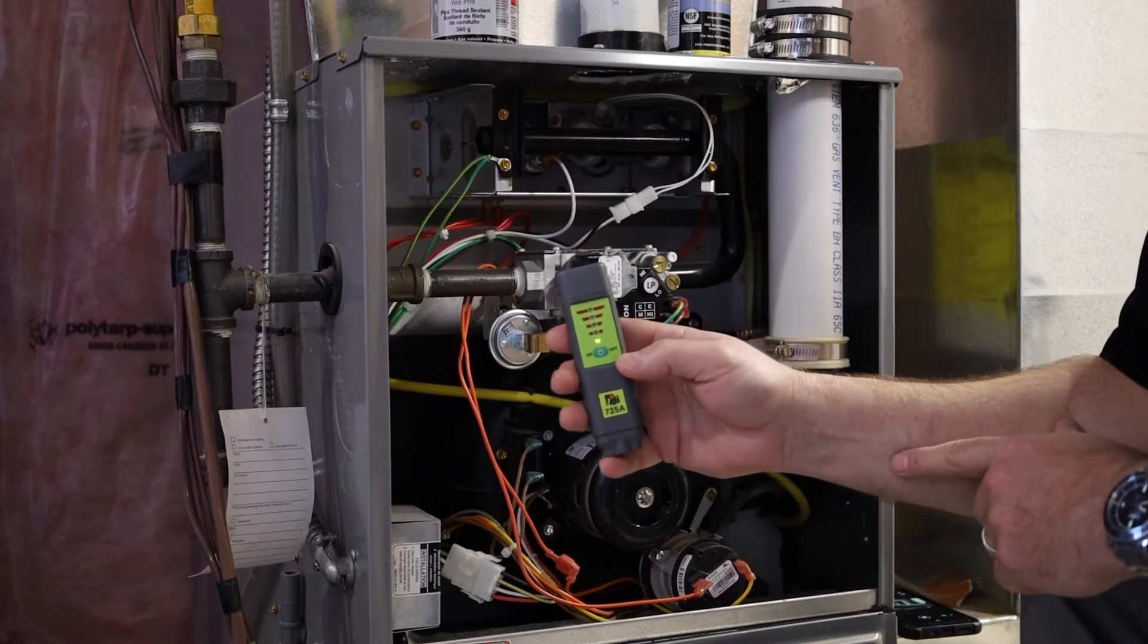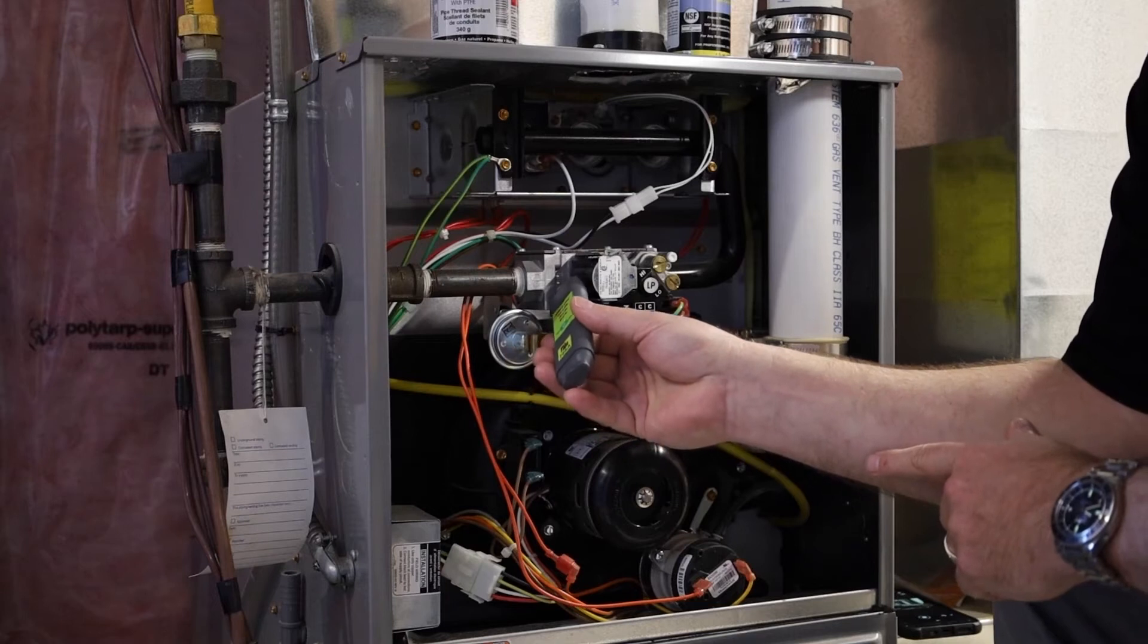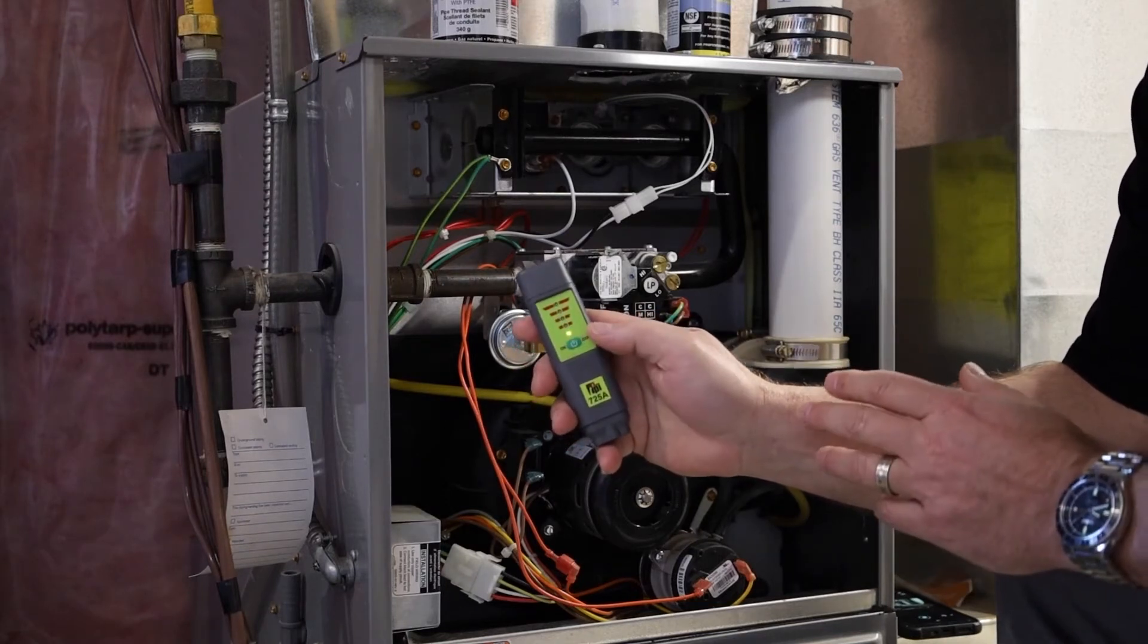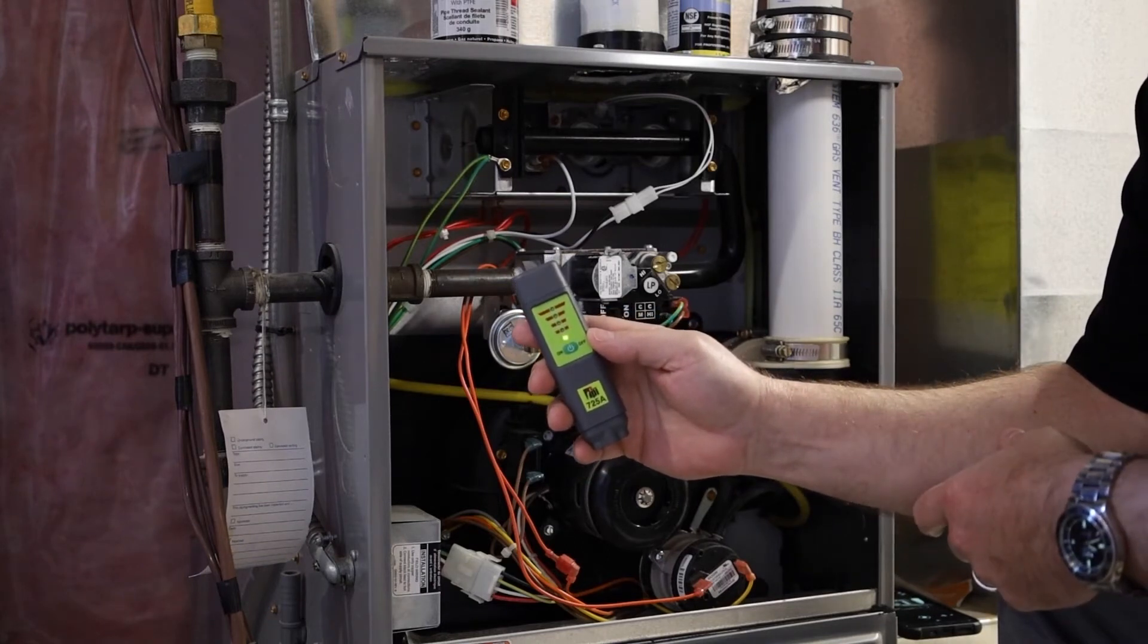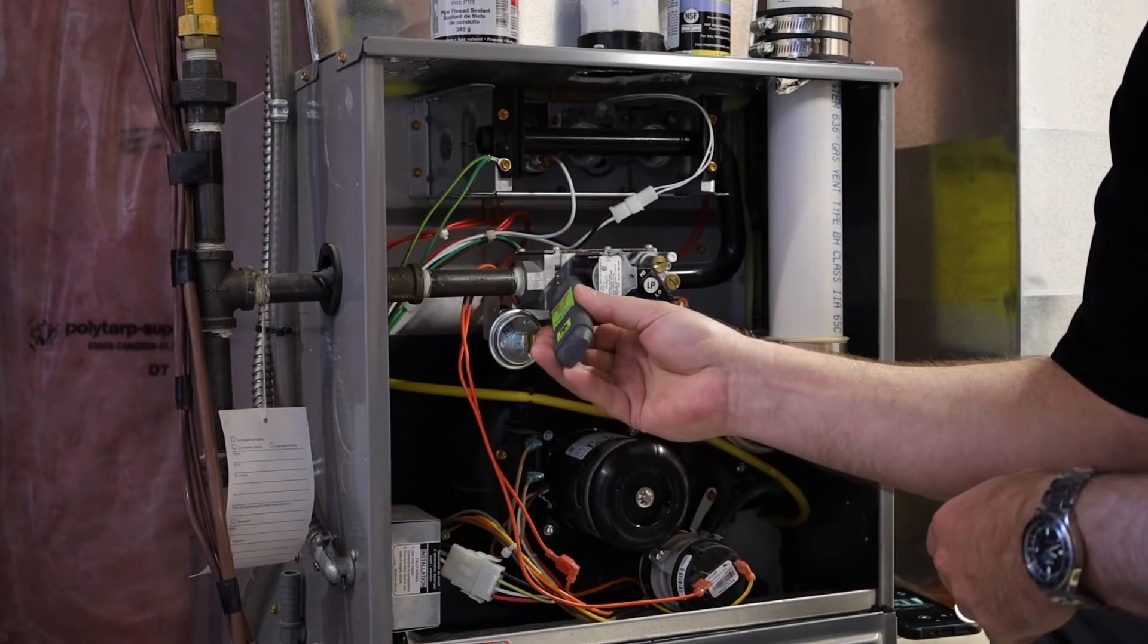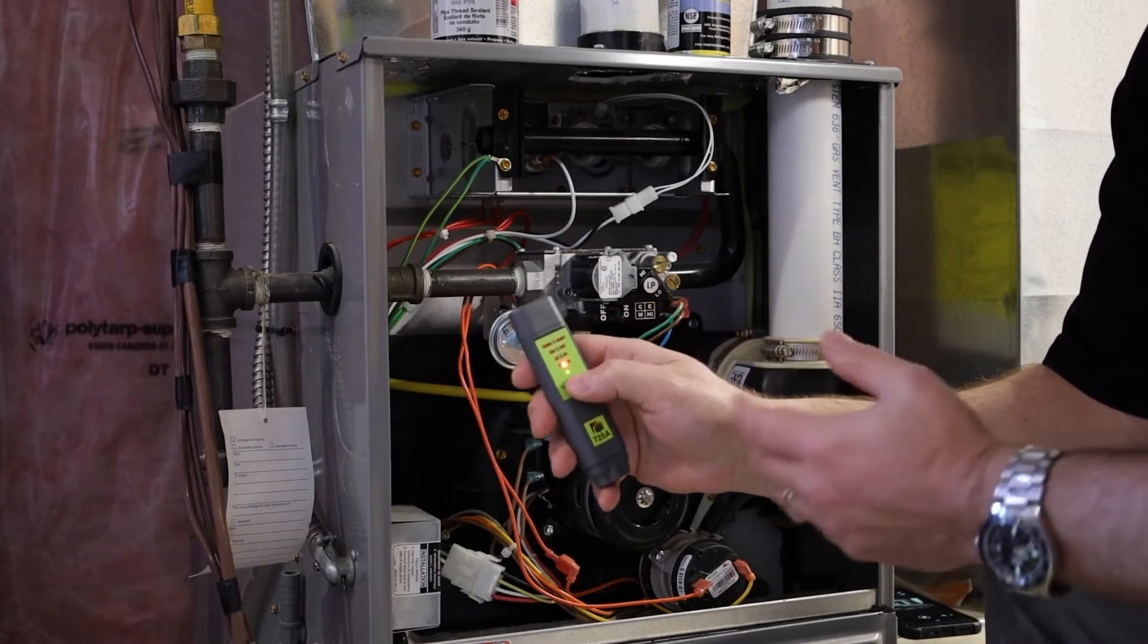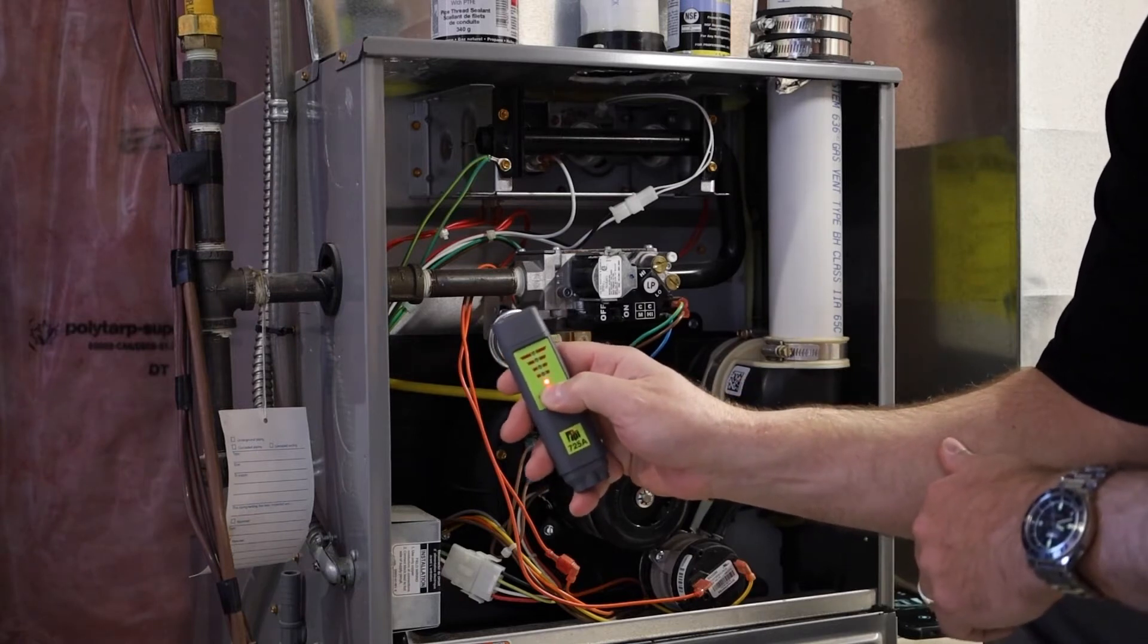Now with this leak detector, when you detect a leak you can press a button and zero it out. So now it is only going to detect higher combustible gases, a higher sample of parts per million. Again go over to my suspected leak and there it goes. Obviously the higher it is, that's where the source of the leak is going to be.